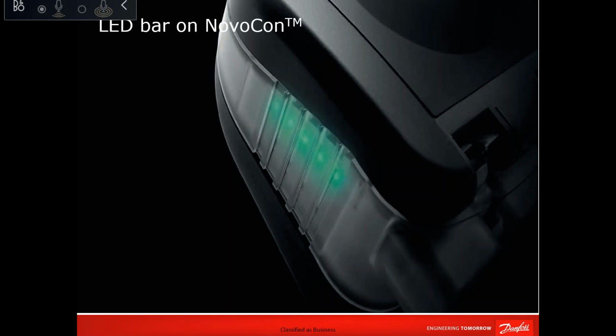Let's say the BMS is not yet ready and you need to do something, or the wiring is done but it's not connected to the BMS, which is most of the project cases. All these alarms we were talking about, the flushing and the movement of the valve, everything can be shown from the local LEDs of the actuator via the color codes. At the side of the actuator, you will see green LEDs blinking, orange, red. Every combination of colors you can check in the datasheet, and you will find it means something.